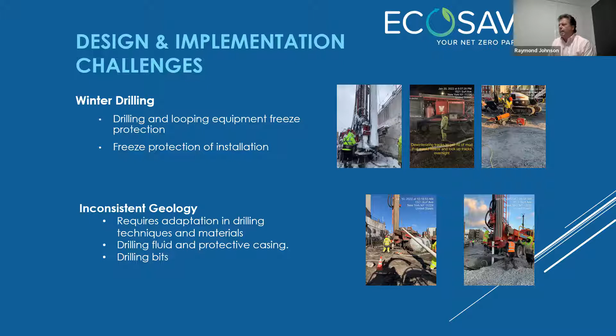Next slide, please. Where we are right now is - an interesting part - we have these wells drilled, and we have to build those into networks. We're fusing those with horizontal pipes that you can see in the drawings below grade. They're fused to each of those wells, tied up and connected to the vertical wells, and then once completed, they're flushed and pressurized to validate the integrity of the system.